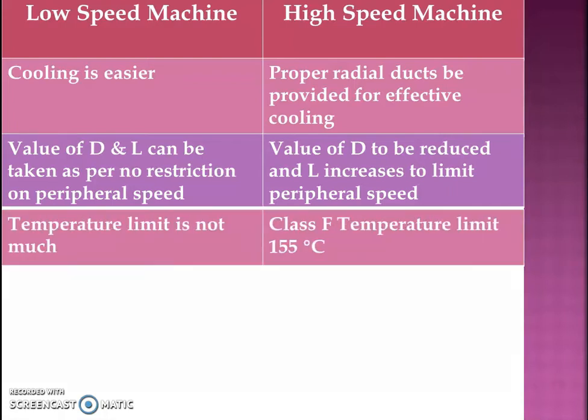Then we have temperature. In case of a low speed machine, the temperature limit is not very important. While in case of a high speed machine, we always use Class F insulation and the temperature limit is 155°C.